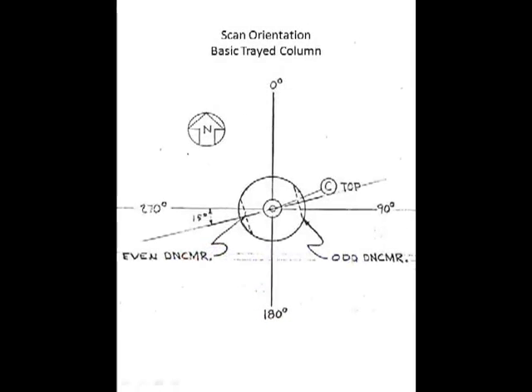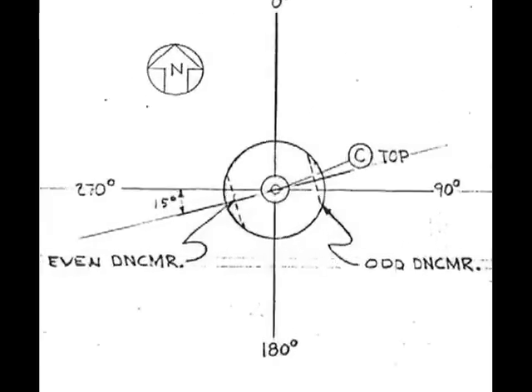This is an example of a gamma scan where the results indicated that tray damage was present. This is a plan view taken from the tower drawings to show the scan orientation.